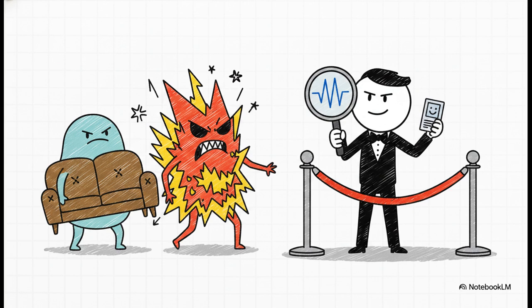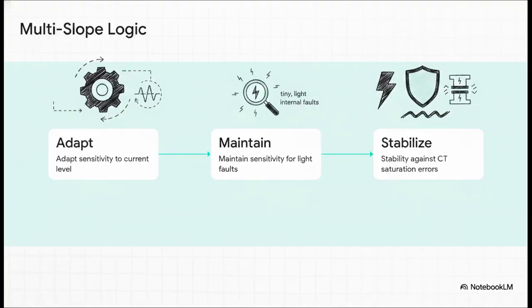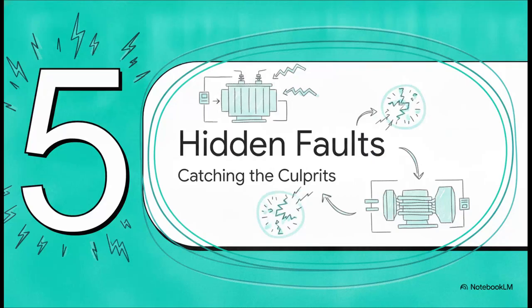That's our magnetizing inrush. And this brilliantly illustrates the concept of multi-slope stabilization that we mentioned earlier. Basically, the relay smartly adapts its sensitivity dynamically based on the current level. It maintains extreme sensitivity for tiny, light internal faults. But if there's a massive fault outside the zone, it actively stabilizes itself. It knows that during heavy external faults, the current transformers measuring the flow might briefly saturate and introduce small errors, so it adjusts its threshold to prevent a false trip. Pretty smart, right?